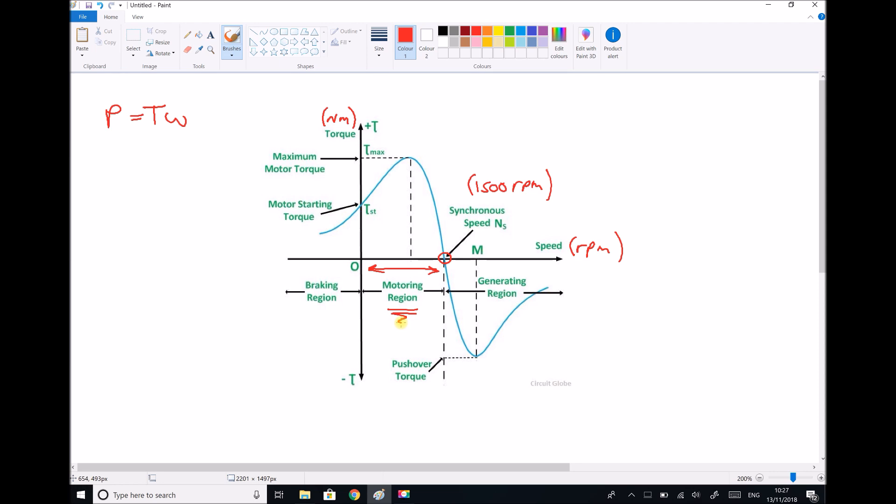The other region of interest is at speeds above 1500 RPM. Above 1500 RPM we're no longer producing torque, we're receiving torque. Instead of using power to generate torque, we're absorbing torque to generate power. It's the same machine, it's just working in an opposing fashion.